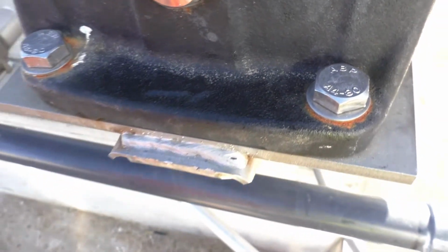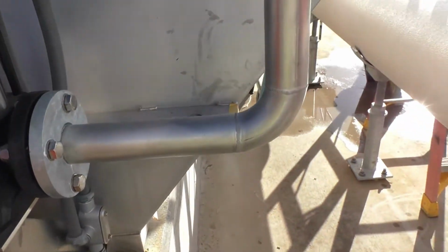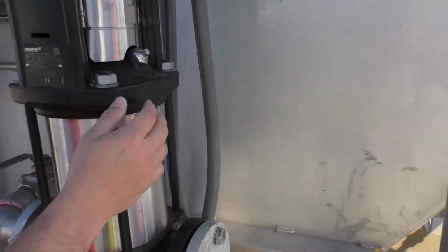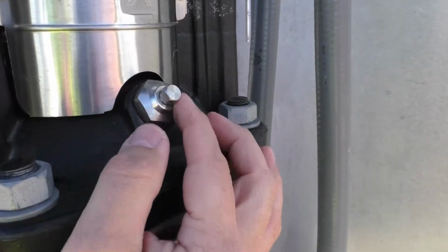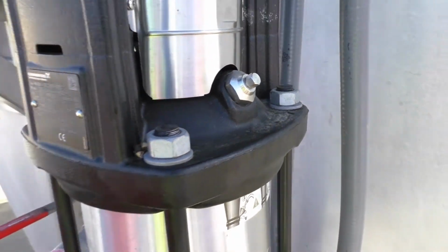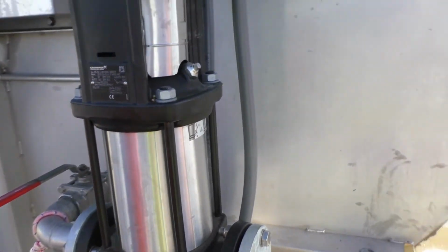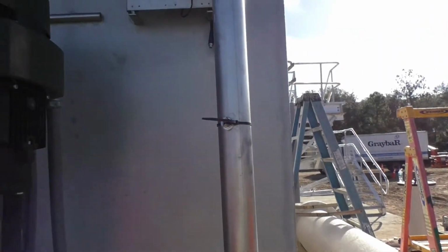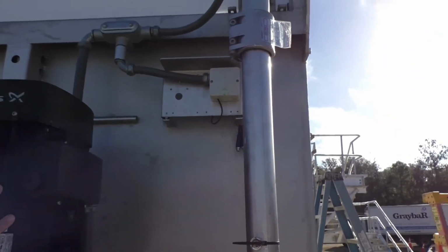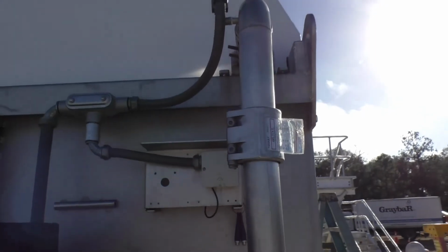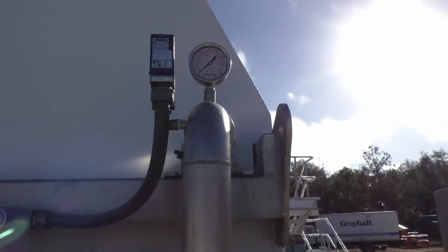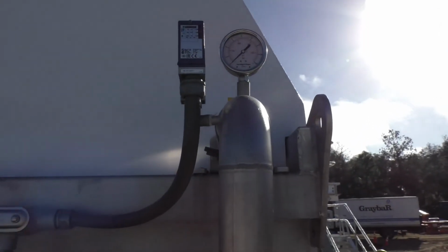So that is basically points your flow. And when you start to fill this up, crack this loose. Before you turn this on, when you crack this loose, water will come in and push the air out to keep it from being airlocked. There's no zerk fittings on this, so no maintenance needs to be done here other than listening to it and just making sure it sounds correctly.